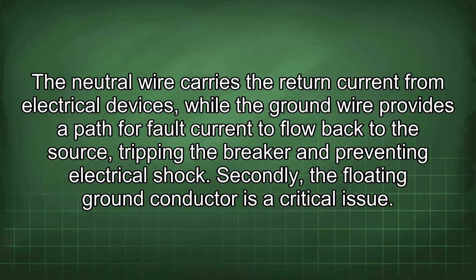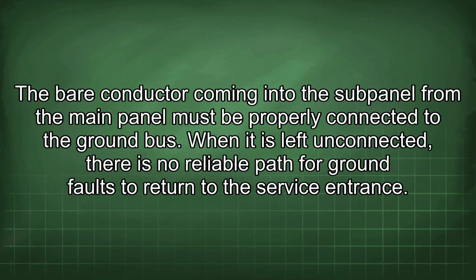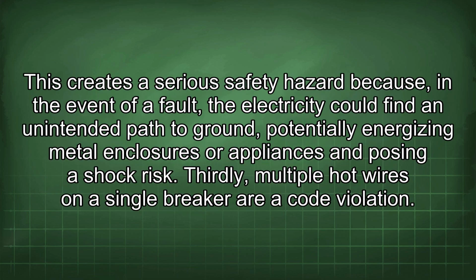Secondly, the floating ground conductor is a critical issue. The conductor coming into the subpanel from the main panel must be properly connected to the ground bus. When it is left unconnected, there is no reliable path for ground faults to return to the service entrance. This creates a serious safety hazard because, in the event of a fault, the electricity could find an unintended path to ground, potentially energizing metal enclosures or appliances and posing a shock risk.